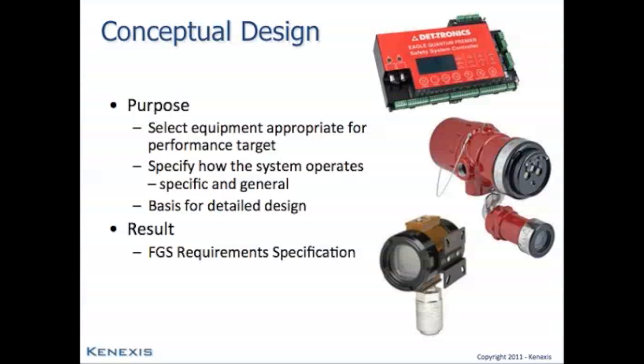What you're doing during the conceptual design stage is selecting equipment that is appropriate for the performance target, and then specifying how the system operates in both specific details for each individual loop, and also general requirements that apply to an overall system. The result of this conceptual design task is going to be an FGS requirement specification that defines all of the FGS functions.